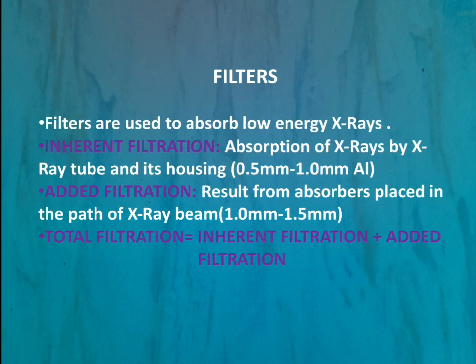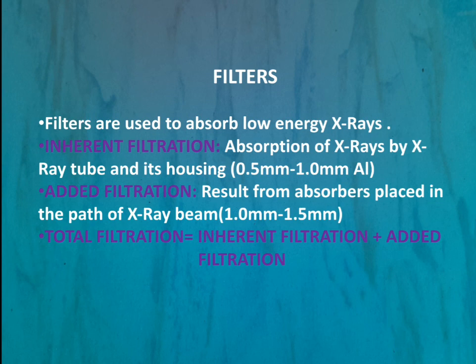To remove low energy x-rays before they reach the patient, we use filters made of aluminium or copper material. Filtration can be of two types: inherent filtration and added filtration. Inherent filtration means absorption of x-rays by the x-ray tube and its housing — x-rays absorbed within the x-ray tube and housing itself. For inherent filtration, 0.5 mm to 1 mm thick aluminium material is used.